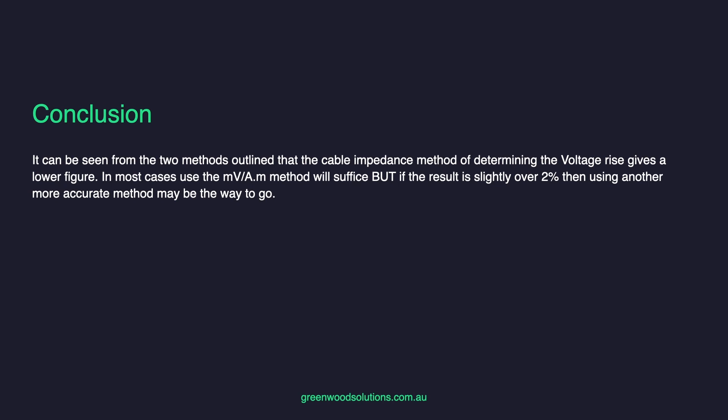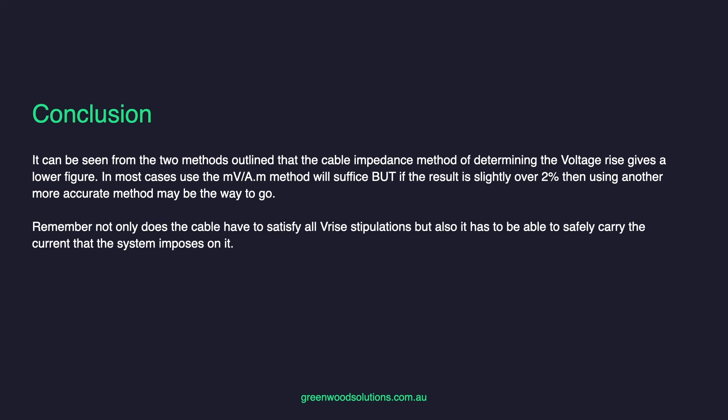It can be seen from the two methods that the cable impedance method of determining voltage rise invariably gives a lower figure. So in most cases, use the millivolt per amp metre method — this will suffice. But if the result is slightly over 2%, then using the more accurate cable impedance method may be the way to go. Remember, not only does the cable have to satisfy all the V rise stipulations, but it also has to safely carry the current that the system imposes on it.